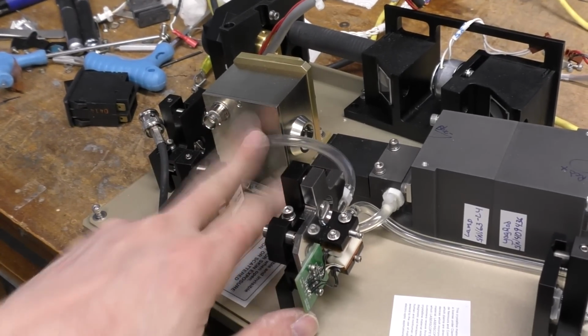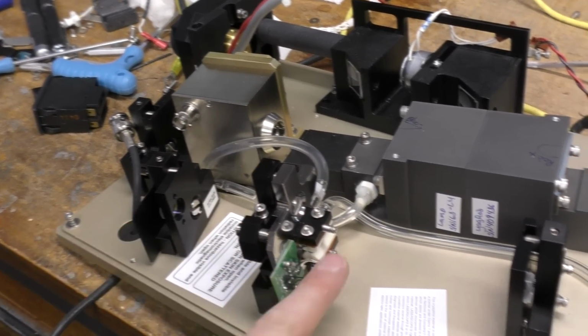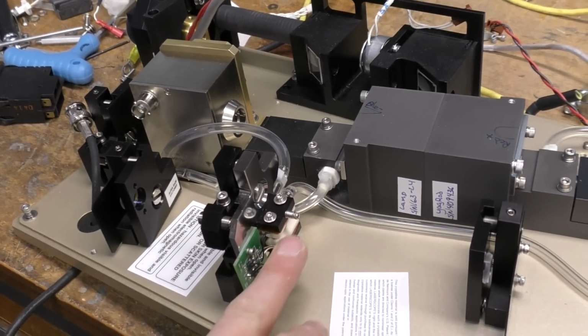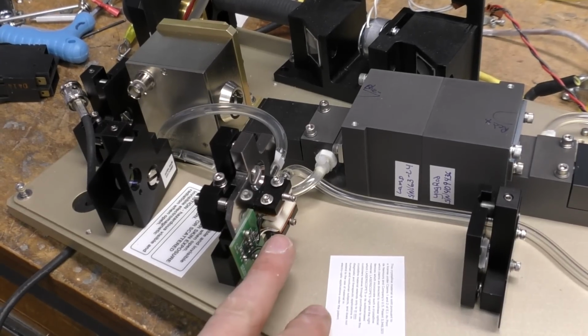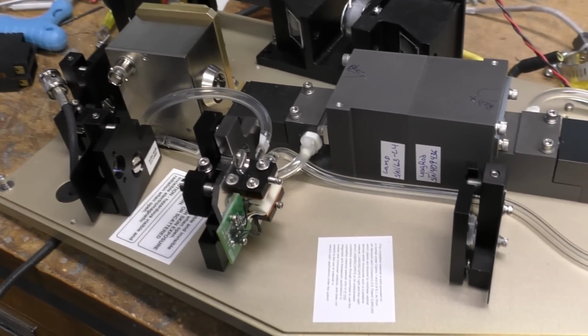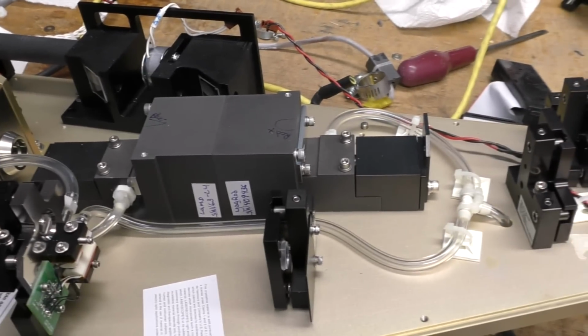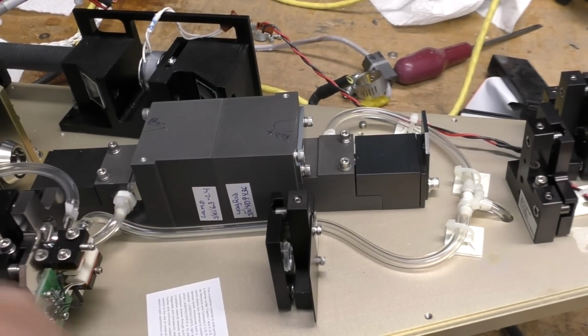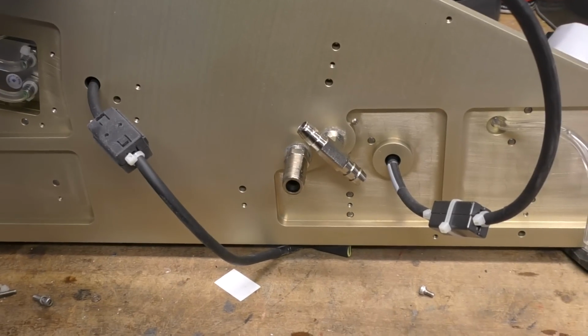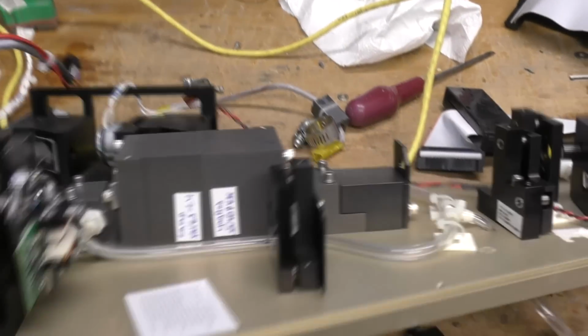And I've got the optical deck off here. You can see some of these cooling tubes going to the Q switch and the heater on the KTP crystal. And there's also a pathway through the main lamp block. But the main cooling comes through here from these bottom tubes. There's 2 thick wires of the main connections to the tube. And this is the lamp block.